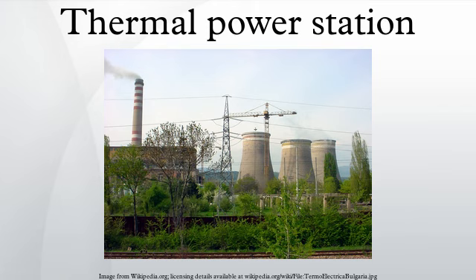Generator cooling. While small generators may be cooled by air drawn through filters at the inlet, larger units generally require special cooling arrangements. Hydrogen gas cooling, in an oil-sealed casing, is used because it has the highest known heat transfer coefficient of any gas and for its low viscosity which reduces windage losses. This system requires special handling during startup, with air in the generator enclosure first displaced by carbon dioxide before filling with hydrogen. This ensures that the highly flammable hydrogen does not mix with oxygen in the air. The hydrogen pressure inside the casing is maintained slightly higher than atmospheric pressure to avoid outside air ingress.